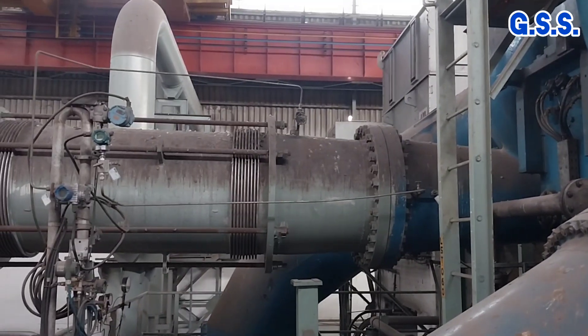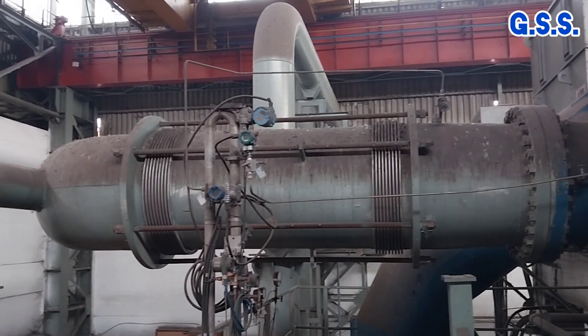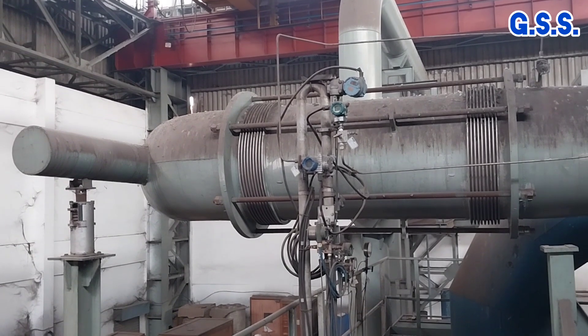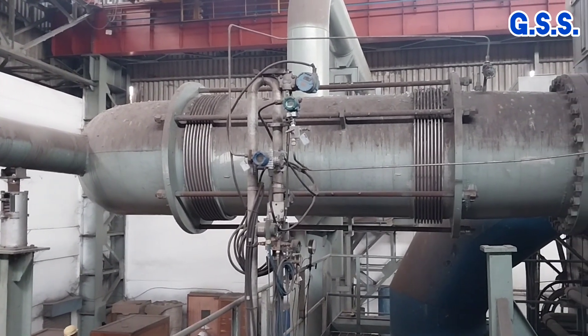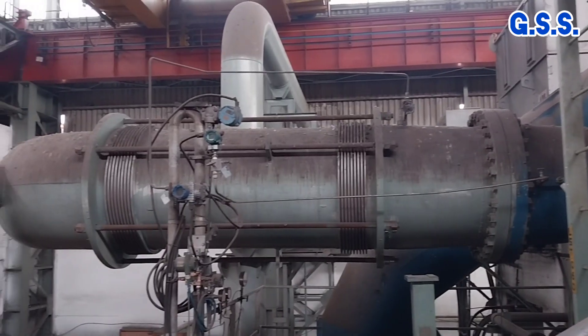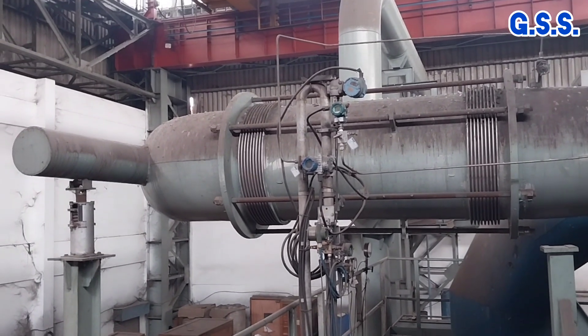If the bellow size is 32 inch — that means 800 mm NB — and the internal pressure is 10 bar, then the axial pressure load will be about 50,000 kg, that means 50 ton.